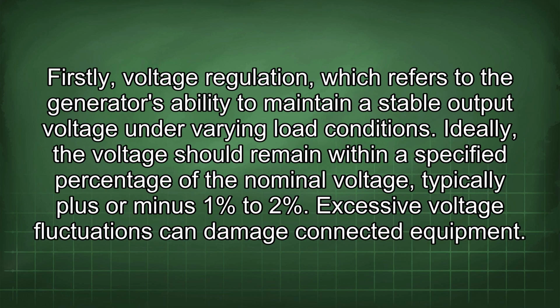Firstly, voltage regulation, which refers to the generator's ability to maintain a stable output voltage under varying load conditions. Ideally, the voltage should remain within a specified percentage of the nominal voltage, typically plus or minus 1% to 2%. Excessive voltage fluctuations can damage connected equipment.